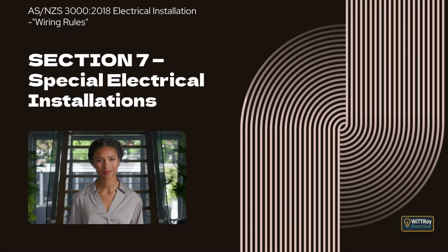Clause 7.4.5 Supply to single item of electrical equipment. This clause explains that where a separated circuit supplies a single item of electrical equipment, any exposed conductive parts of that equipment must not be connected to exposed conductive parts of any other circuit, including other separated circuits, or to earth.